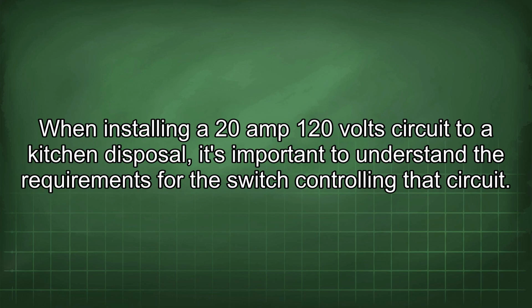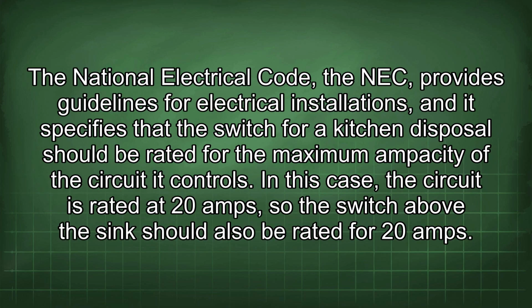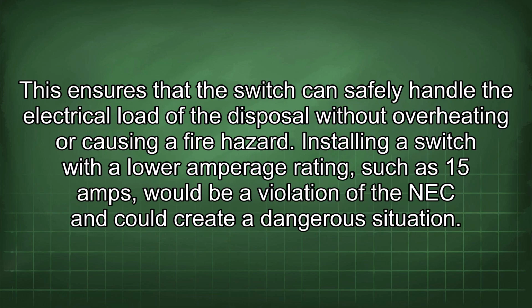When installing a 20-amp 120-volt circuit to a kitchen disposal, it's important to understand the requirements for the switch controlling that circuit. The National Electrical Code, the NEC, provides guidelines for electrical installations, and it specifies that the switch for a kitchen disposal should be rated for the maximum ampacity of the circuit it controls. In this case, the circuit is rated at 20 amps, so the switch above the sink should also be rated for 20 amps. This ensures that the switch can safely handle the electrical load of the disposal without overheating or causing a fire hazard. Installing a switch with a lower amperage rating, such as 15 amps, would be a violation of the NEC and could create a dangerous situation.